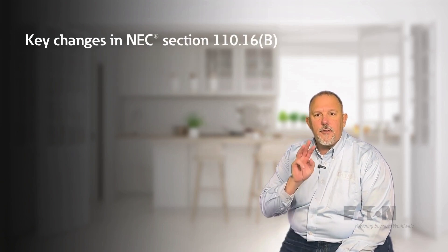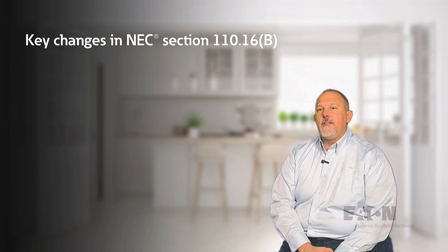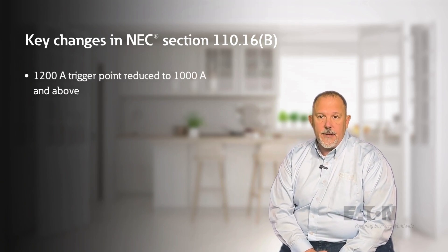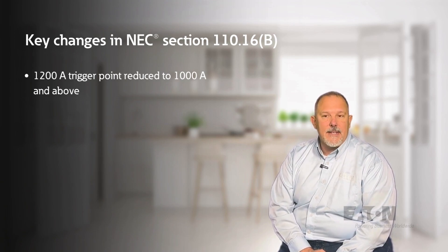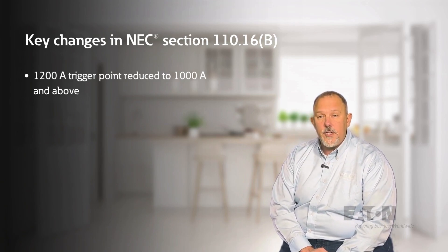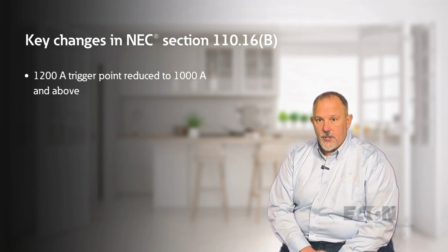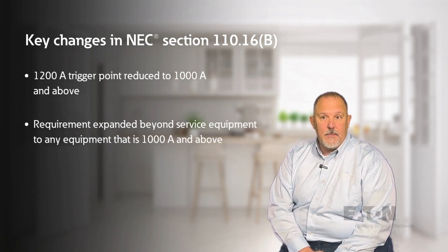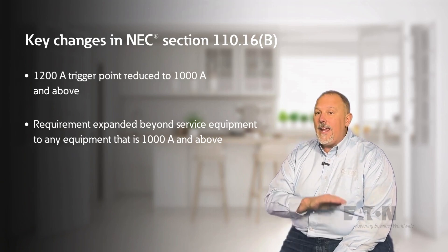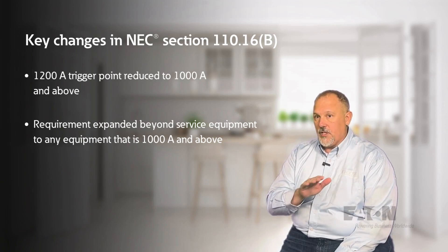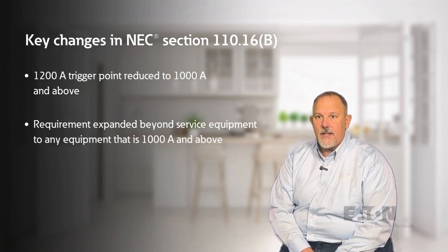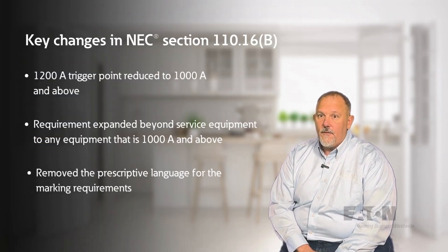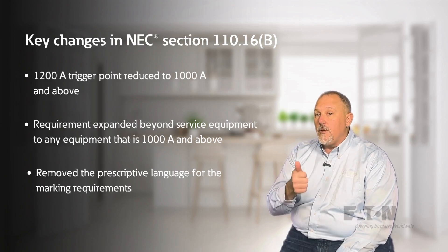NEC 2023 introduced three major changes to 110.16(B). First, the 1200 amp trigger point was reduced, impacting panel boards, switchboards, and switchgear 1000 amps and larger. Second, this requirement was expanded beyond service equipment to any panel board, switchboard, and switchgear 1000 amps and larger.